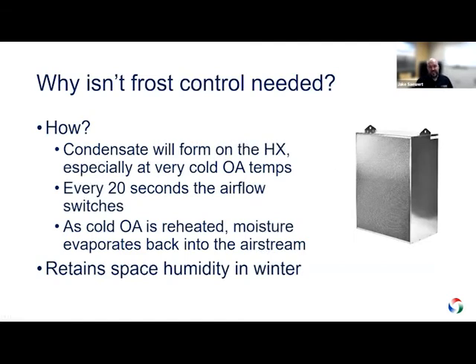Mentioned before that frost control is not needed with this device, and it's a valid question of, well, how is that possible? In normal operation in cold climates, you're actually going to get condensate that starts forming in your return air. But because that cycle flips every 20 seconds, as that outdoor air comes in and actually starts to heat up, it's going to take on all of that condensate and evaporate it into the airstream. So what ends up happening is you actually end up retaining the moisture that normally you'd be exhausting into the atmosphere. So what ACCUBLOC has seen is that in many applications, it retains a higher space humidity, even when it's not mechanically humidified, just by the fact that you're not exhausting it out and then you keep recapturing it. So it all has to do with the cycle. That's why a form of frost control isn't required.